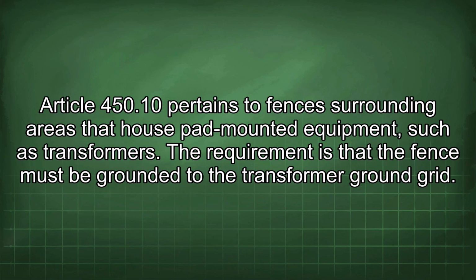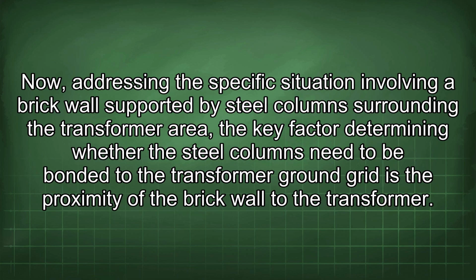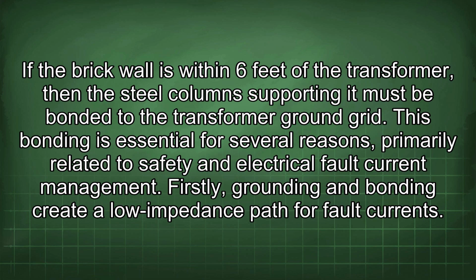Article 450.10 pertains to fences surrounding areas that house pad-mounted equipment, such as transformers. The requirement is that the fence must be grounded to the transformer ground grid. Now, addressing the specific situation involving a brick wall supported by steel columns surrounding the transformer area, the key factor determining whether the steel columns need to be bonded to the transformer ground grid is the proximity of the brick wall to the transformer. If the brick wall is within 6 feet of the transformer, then the steel columns supporting it must be bonded to the transformer ground grid.